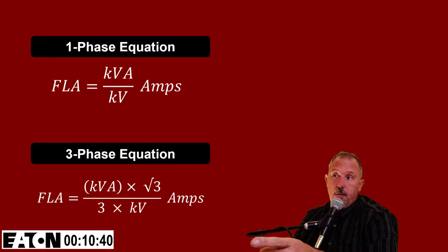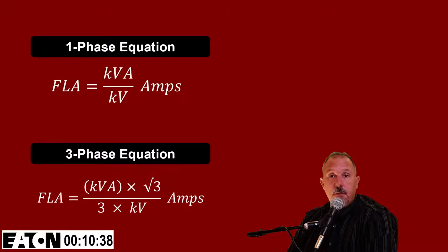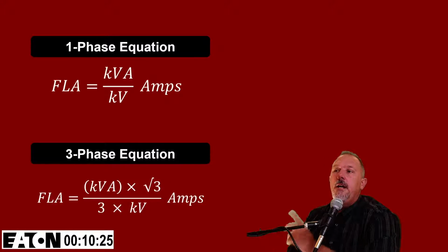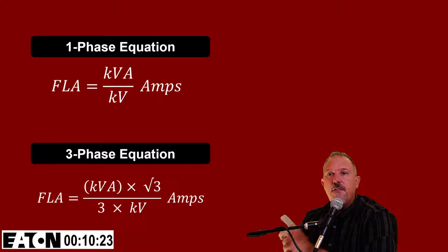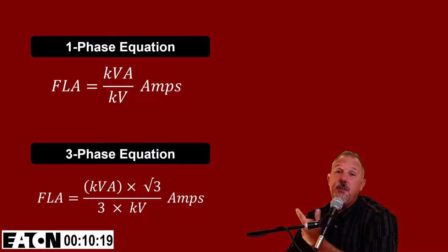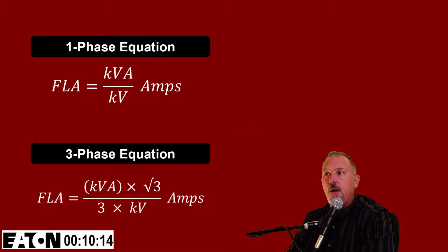If you look at that equation for full load amps, you're dealing with a three-phase transformer. So the first step is to get it to a single-phase transformer. So it's kVA over 3 gets me a single-phase kVA. My secondary three-phase kV, which I probably should put kV three-phase there, to get to single-phase, I have to divide that number by the square root of 3. And because it's in the denominator, the square root of 3 goes to the numerator. So that's why you've got kVA times square root of 3 over the kV.